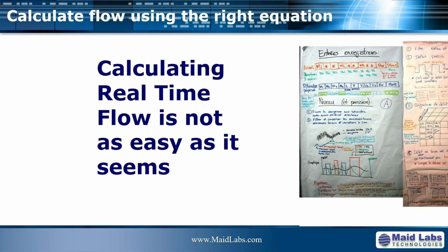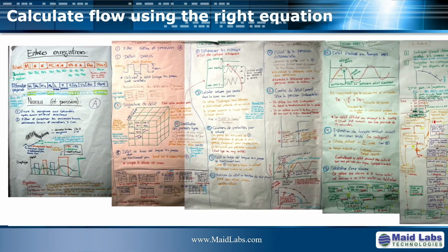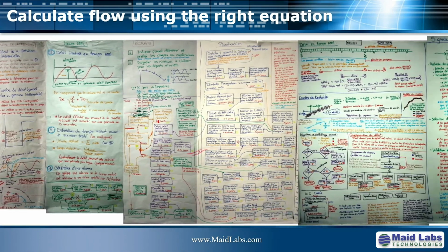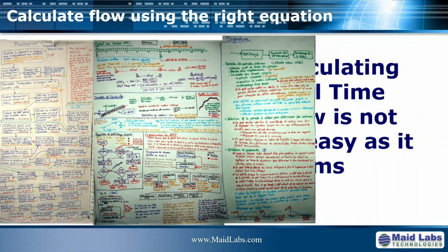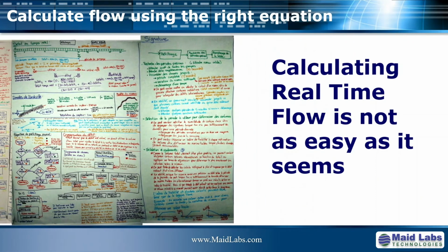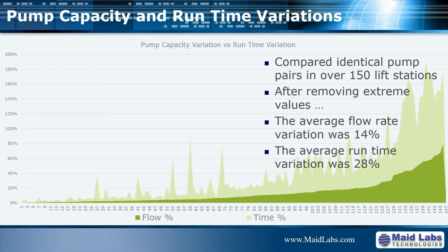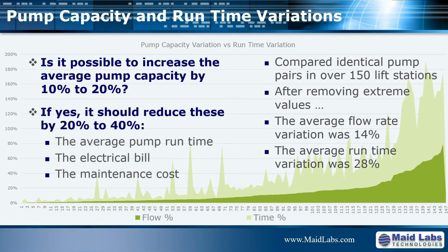It's not just volume divided by time. That would be what I did back in the early 1980s. So you have to do something different when you want to compensate for abnormal behavior and if you want to have high accuracy. One thing I did not too long ago, I decided to analyze pumps within over 150 lift stations just to figure out, when there was a difference in pump capacity, what was the difference in pump run time, and arrived at a rule of thumb that for every percentage difference in pump capacity, you had twice that difference in pump run time. So if you can increase the pump capacity by only 5%, you will decrease the pump run time by 10%.